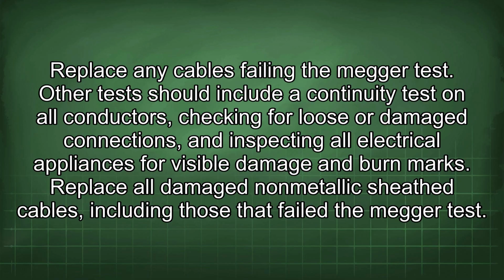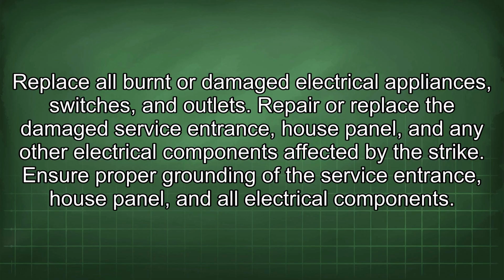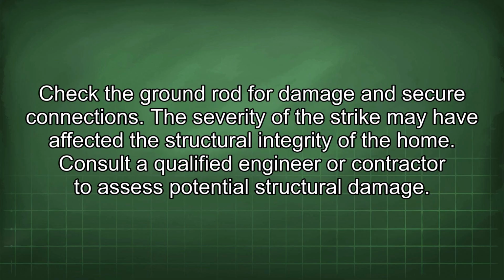Replace all damaged non-metallic sheath cables, including those that failed the megger test. Replace all burnt or damaged electrical appliances, switches, and outlets. Repair or replace the damaged service entrance house panel and any other electrical components affected by the strike. Ensure proper grounding of the service entrance house panel and all electrical components. Check the ground rod for damage and secure connections.